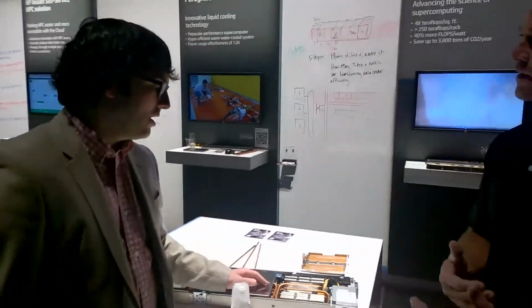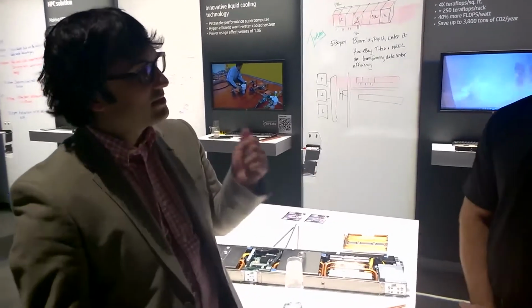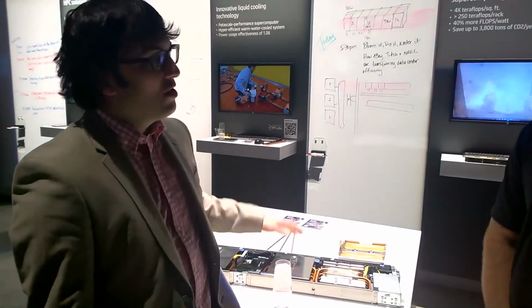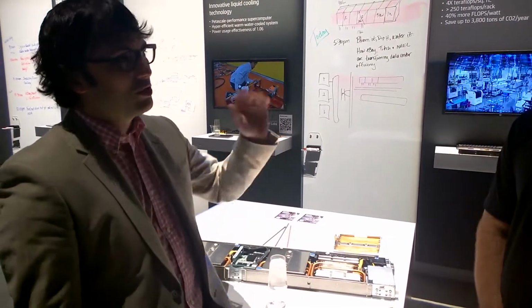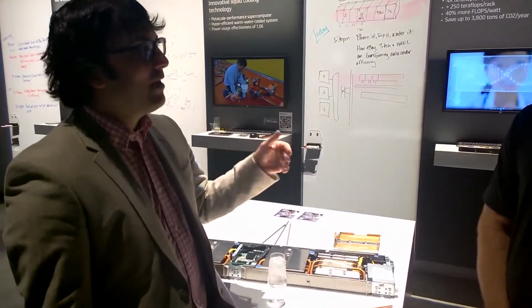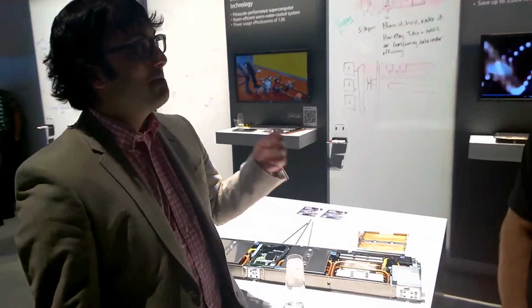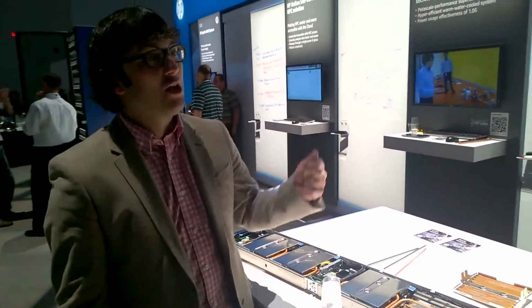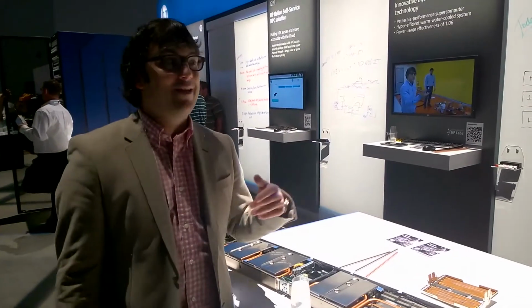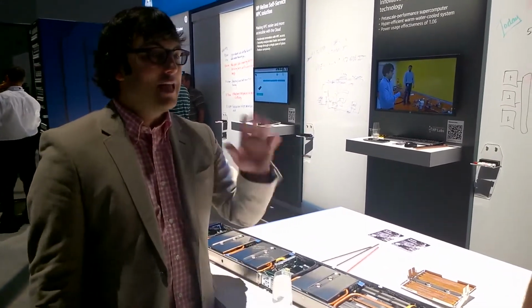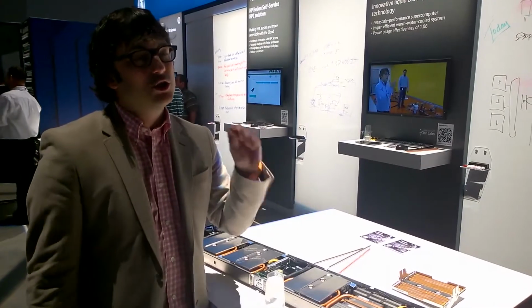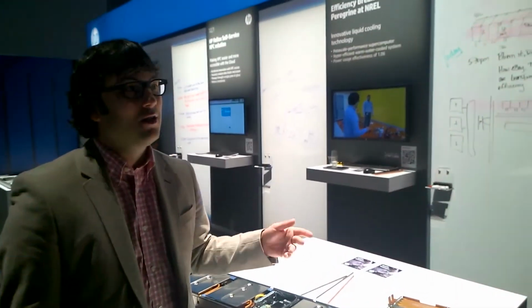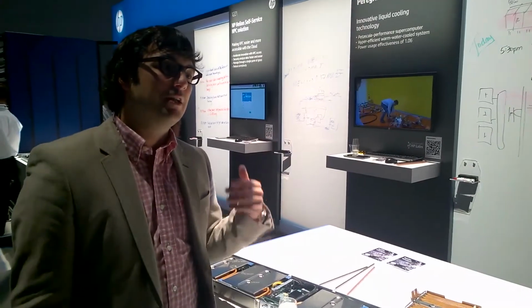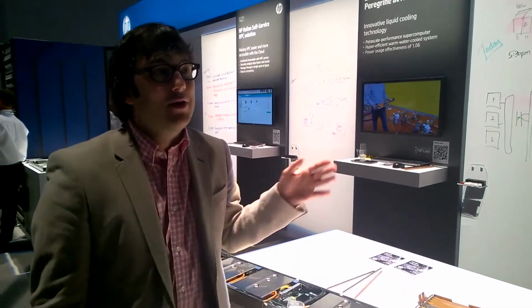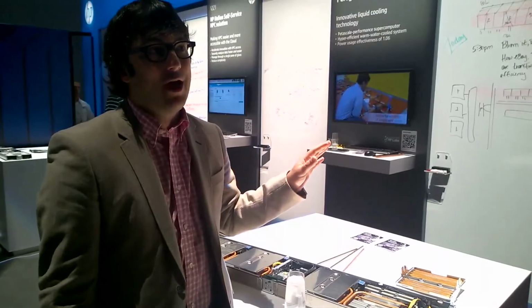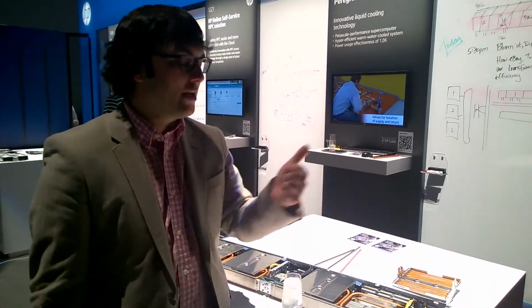Now why water-cooled versus air-cooled? So there's mainly three aspects. The first one is energy efficiency. With a water-cooled server, you're able to supply an Apollo system with 80 to 85 F water year-round, meaning that you don't need chillers. If you're saving chillers in your data centers, you're looking at saving a lot of energy. That system can run in most geographies solely on dry coolers or evaporative towers. NREL, our prototype system in Colorado, has no chiller at all in their 10 megawatt data center. It's purely evaporative towers. So that's advantage number one.